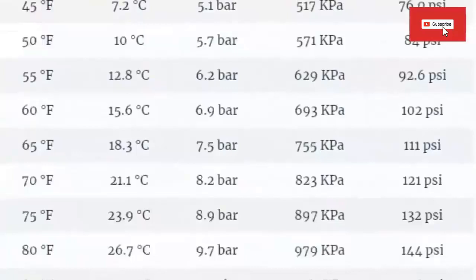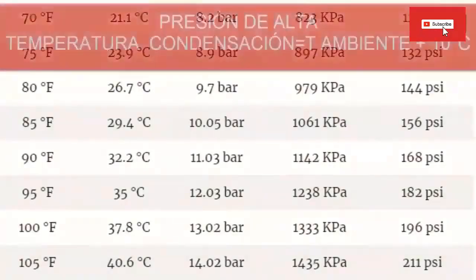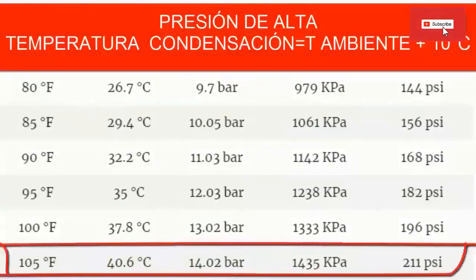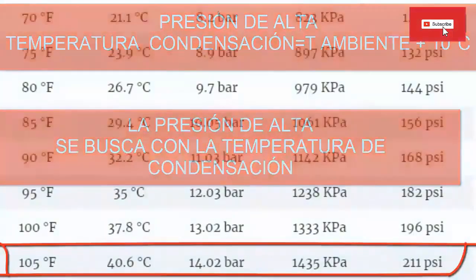Now we look for the high side pressure in the table. Taking an external ambient temperature of 30 degrees Celsius, we increase this value by 10 degrees Celsius and look in the table for approximately 40 degrees Celsius. This gives us a pressure of approximately 211 psi, equivalent to 14 bar.